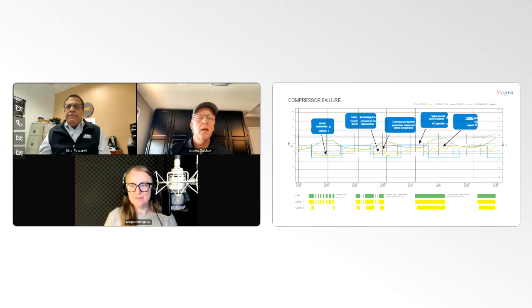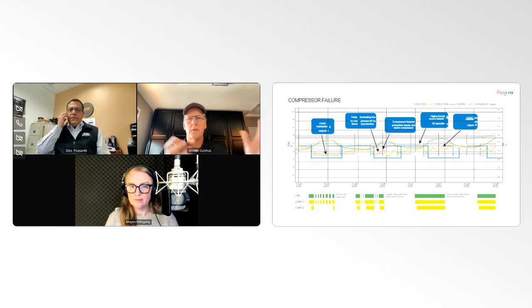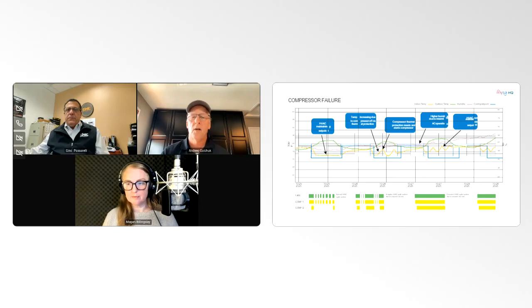Andrew, any thoughts there? Yeah, I think the reality is compressor failure can happen over time. It can be a gradual event, or it can be immediate. I think really the best approach, as you were mentioning, is maintaining the system overall. Even though the compressor itself may be functioning well, having dirty condenser coils, for example, is going to stress that compressor and just reduce the overall lifespan of it. So maintenance is definitely important for sure.